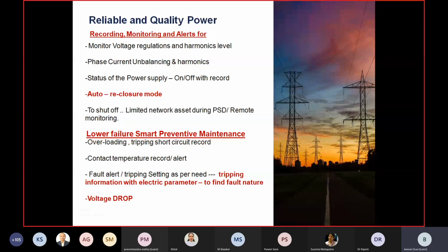Even for smart preventive maintenance, I need records of overloading, how many short circuit trippings there were, how many fault level trippings, what the contact temperature was, so I can plan whether I need to do preventive maintenance once a year, thrice a year, once in 3 years, or once in 4 years.